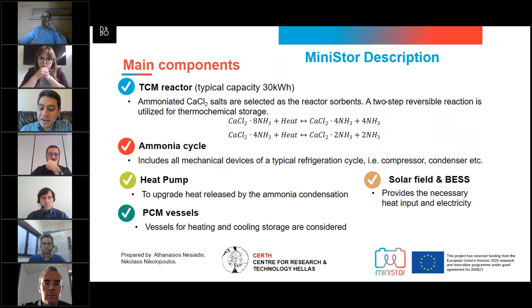The ammonia cycle includes all the mechanical devices used in a typical refrigeration cycle, such as a compressor, condenser, heat exchangers, etc. We also have a heat pump that upgrades the heat released by the ammonia condensation. There are phase change material vessels that provide parallel heat storage depending on location, either with heating and cooling or just heating. The solar field and battery storage produce the required input and electricity.